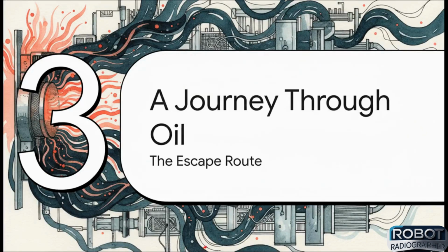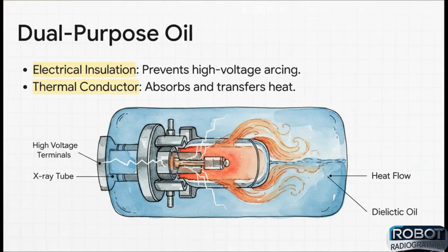Okay, so the anode has absorbed that initial blast, but now all that heat is trapped. The next problem is getting it out. So let's follow the heat on the first step of its escape route, a journey through a very special kind of oil. The whole X-ray tube assembly is literally bathed in something called dielectric oil, and this stuff is a fantastic piece of multi-purpose engineering. First, it's an amazing electrical insulator, which stops the system's high voltage from arcing and zapping itself. But second, and just as important, it's a thermal conductor. It actually pulls heat off the hot glass of the tube and starts moving it away toward the outside.